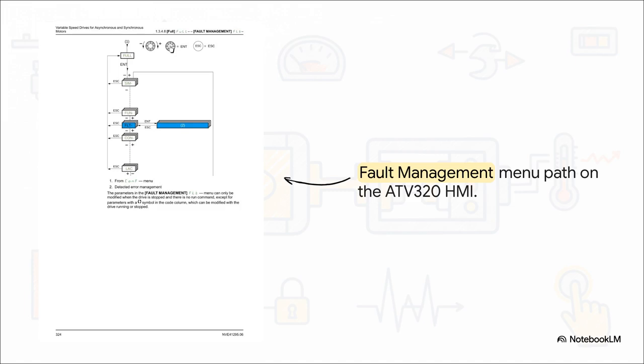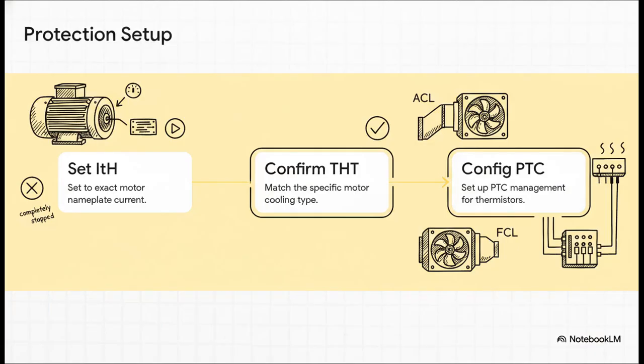If you're standing in front of the drive, you're going to use the jog dial on the front panel to navigate. You'll want to scroll over to the Conf menu, which stands for Configuration, press the dial to enter the full menu, and then scroll your way down into FLT, that's the Fault Management menu, and this entire section is dedicated to setting up your safety boundaries. Now here is a vital rule of thumb. These fault parameters can only be changed when the drive is completely stopped. Make sure there's no run command active or the drive will just lock you out.